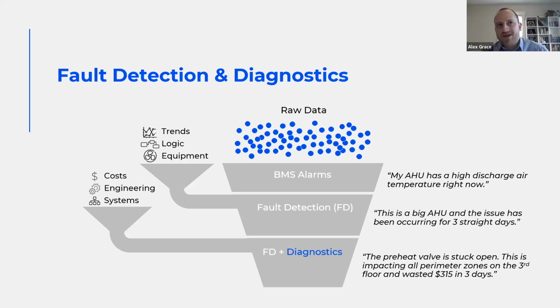When we get to the diagnostic layer, now we're adding more to the equation — adding costs, the ability to quantify what this is worth, and more knowledge of engineering and systems to get to that root cause. So you might get an output like this: the preheat valve is stuck open, this is impacting all perimeter zones on the third floor, and this has wasted $315 in the last 3 days.